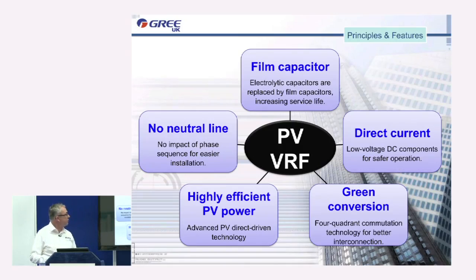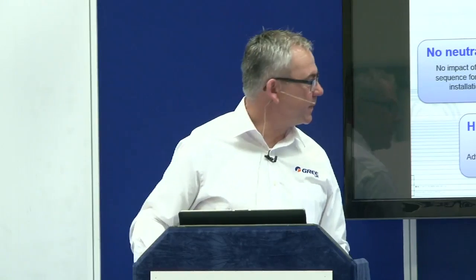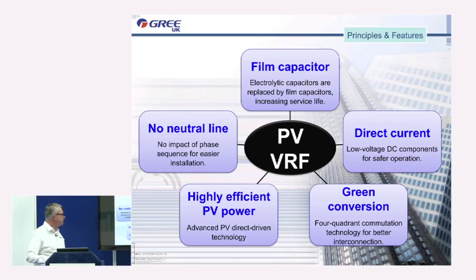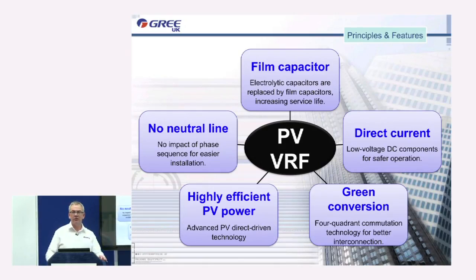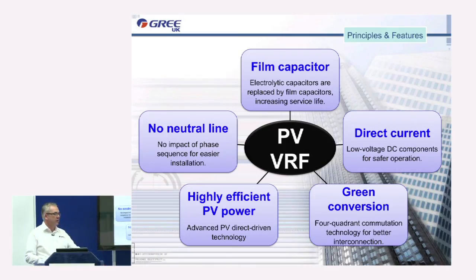We also have direct current, low voltage DC components for much safer operation within the system. We have what we call 4-quadrant commutation technology for better interconnection. So this means that basically we are able to control and manage the DC voltage and the AC voltage very easily. High efficient PV power, so advanced PV direct driven technology, which again all adds to the control of the PV generated power. And then lastly, no neutral line, so this reduces costs, reduces losses, and allows us to control the power in a much better way, increases our power factor and reduces our losses.